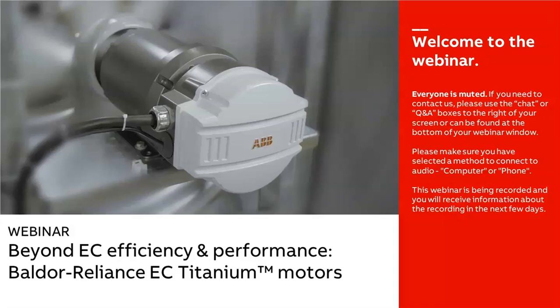And what you're probably asking too is that traditional EC motors, being DC, put out harmonics at non-traditional points, and so they're very difficult to actually filter. With this product being a standard PWM controller, it has harmonics that a standard harmonic filter will easily mitigate, or you could simply add some input impedance ahead of the drive with a reactor, just like you do with most PWM drives. But it's not built into the product, so any harmonic mitigation would be external.